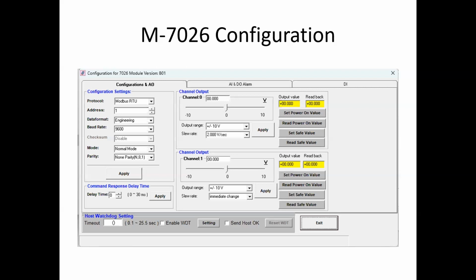It's very easy to add devices to an existing Modbus TCP network, whereas with Modbus RTU, you need to plan the wiring and be aware that you can only have one Modbus RTU master at a time, so only one software package or PLC can communicate to it at one time. If, for instance, you wanted to do both, you need to set up your PLC as a Modbus RTU master to read from the devices and output it to, say, a SCADA system like InduSoft or AVEVA Edge. So it gets a little more complex, whereas if you had Modbus TCP slaves, you can read the data from the devices directly. So again, I prefer Modbus TCP over RTU.